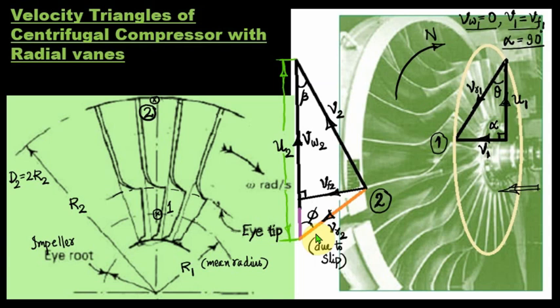That is due to a very special phenomenon, by considering the slippage, or you say slip factor. There is a recirculatory flow of air around the blade surfaces due to the inertia effect. Due to the inertia effect, air is flowing radially out, and the impeller at very high speed is rotating in this direction. So there is a pressure difference created on both surfaces, just like the two sides of an aerofoil. We considered in the case of mechanics of fluids flow over aerofoils, the pressure difference on the upper surface and lower surface. Similar to that, here on both surfaces of the blade there is a pressure difference due to which there is a recirculatory flow. So keep in mind, because of the inertia effect, there is a recirculatory flow.